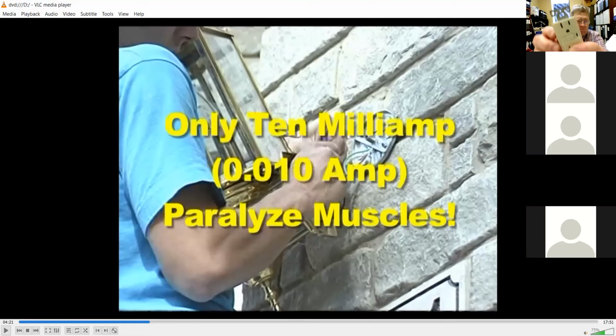So look, this ground fault receptacle trips somewhere in the range of 4 to 6 milliamps. So it trips before you hit 10 milliamps going through your body. That's the reason why this is designed with a particular trip level below 10 milliamps. These are designed several milliamps below 10 milliamps. Now you could have 2 or 3 milliamps of leakage current and this would not trip. But if you got between 4 and 6, somewhere in that range, that's where that GFCI is going to trip.